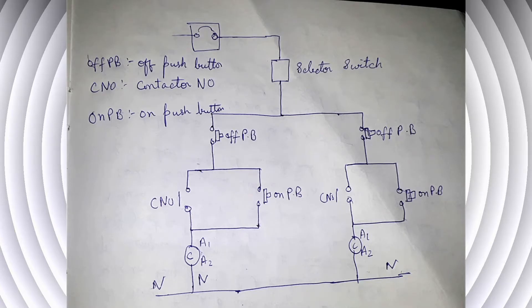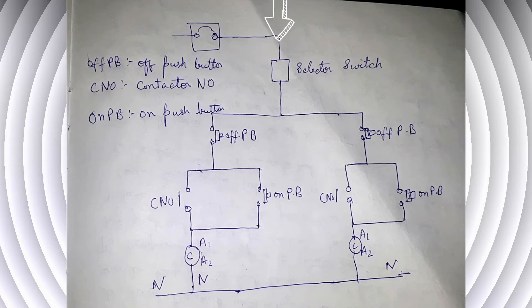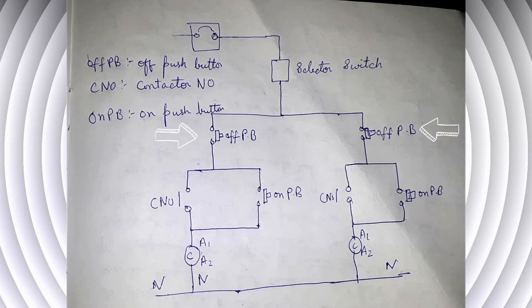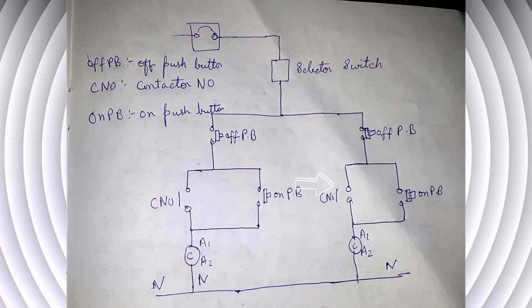Now I am explaining the control circuit of this DOL starter — this is an extra part of the video. From the 6-ampere single pole circuit breaker we connect to the selector switch, and from the selector switch to pump 1 and pump 2. For pump 1: from selector switch to the OFF push button, then from the OFF push button two wires are taken — one connects to the contactor NO and another to the ON push button. From the ON push button, one wire connects to the NO of the contactor and another to A1 of the contactor.